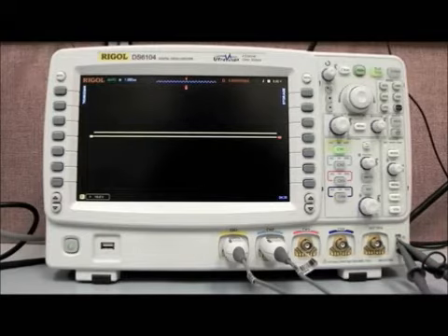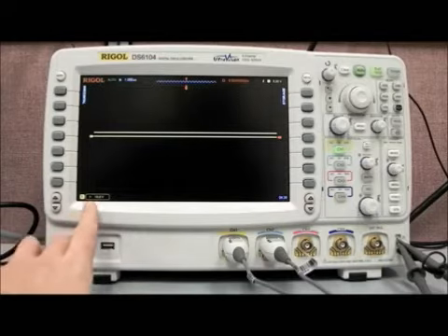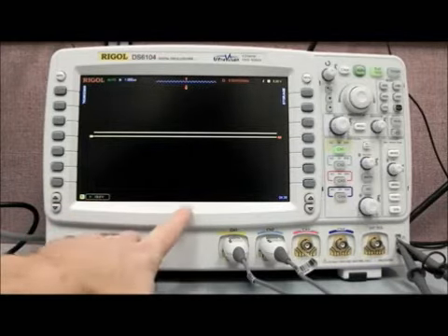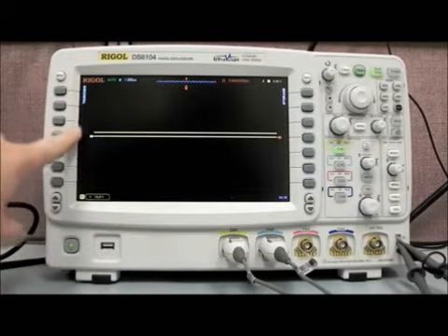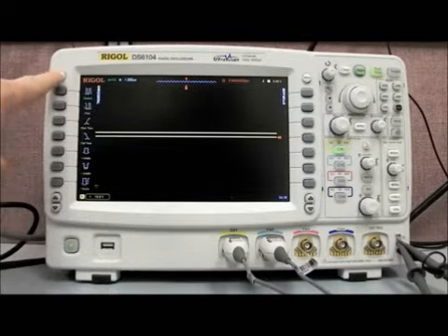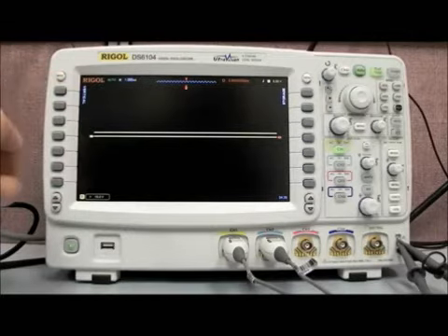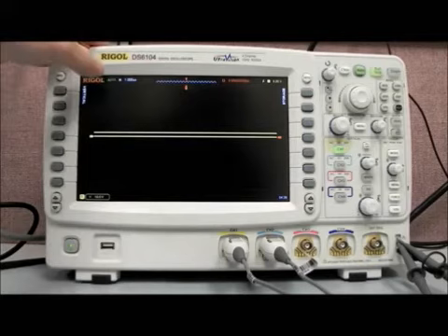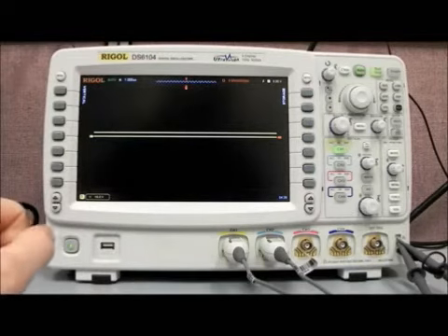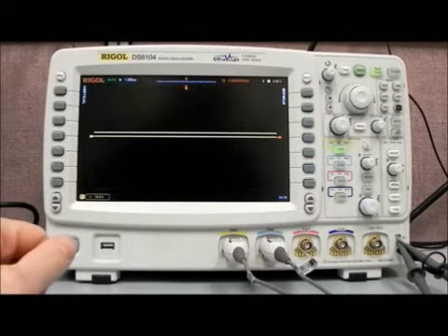I'd like to describe in a little more detail what we see on the screen for the DS6000. On the lower left-hand corner, we have denoted the channels and their voltage settings. We have a quick menu on the left-hand side for horizontal as well as vertical measurements. We have the auto trigger. This denotes when the instrument is triggered, and also the trigger mode that we may have enabled.